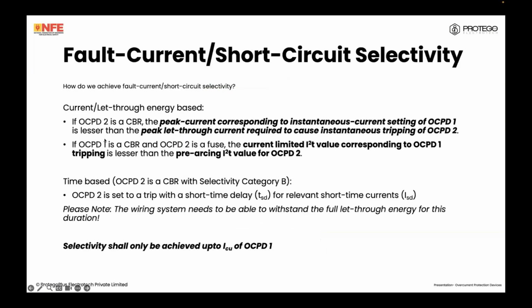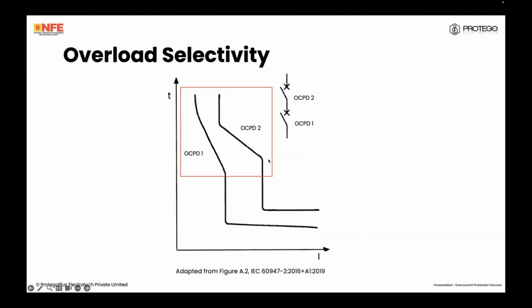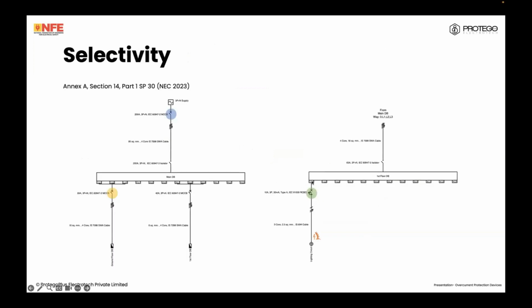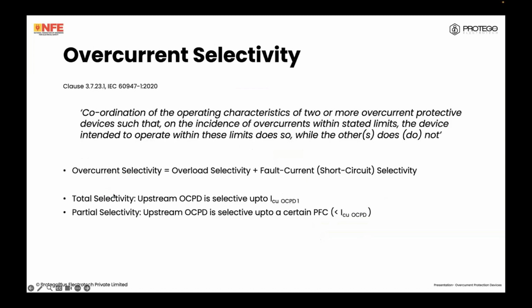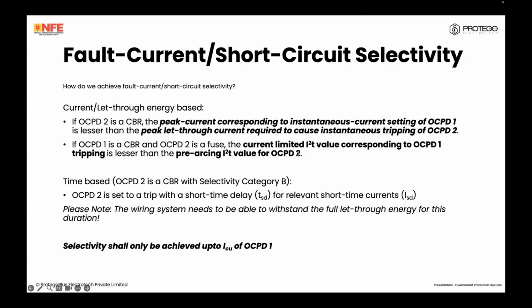That is very easy. If OCPD1 is a circuit breaker and OCPD2 is a fuse, for fuses we have to compare the let-through energy. We have to ensure that the current limited I square T value corresponding to OCPD1 tripping is less than the pre-arcing I square T value of OCPD2. So we'll go back here. When there's a fault, we have to ensure that the let-through energy here under the fault is less than the peak let-through energy required to trip here. I will repeat: the current limited I square T value corresponding to OCPD1 is lesser than what is called the pre-arcing, just before it arcs, I square T value of the fuse, OCPD2. I'll show you an example ahead.